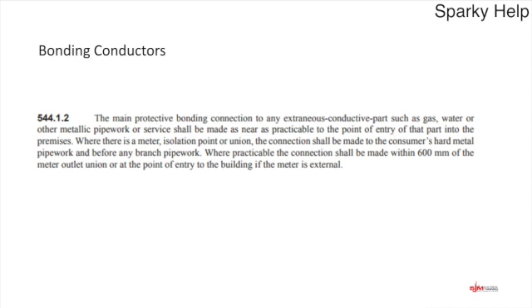And what it's basically saying is we should bond them as practical as near to the point of entry into that premises. And it says where there is a meter, isolation point or union, the connection shall be made on the consumer's hard metal pipework and before any branch pipework. Where practicable, the connection shall be made within 600mm of the meter outlet or the point of entry to the building if the meter is external.